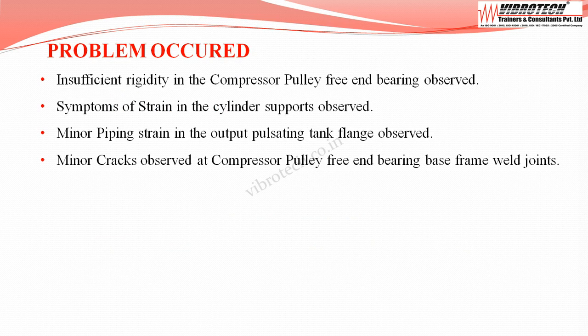On physical inspection: insufficient rigidity in the compressor pulley free end bearing was observed. Symptoms of strain in the cylinder supports were observed. Minor piping strain in the output pulsating tank flange was observed. Minor cracks were observed at the compressor pulley free end bearing base frame weld joints.